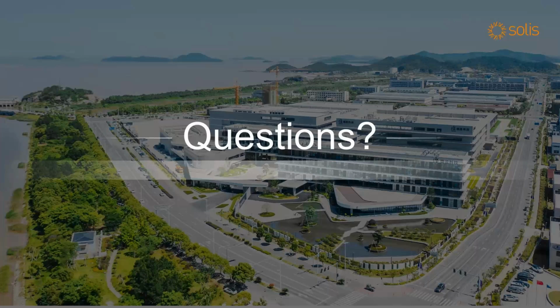And my final recommendation on that, Jason, is that if you look at our data sheets, you'll see that all of our inverters have a DC voltage rating. For example, on our hybrids it's around 330 volts. And then you'll see that it has a max input current. This is the max current that you can send to our MPPT without clipping. So for example, on the 14 amp 10K inverter, 330 times 14 amps is about 4,600 watts. That's what you can do to always determine the manufacturer's recommended power limit for any of our MPPTs. So take a look at our data sheets and you'll see, again, rated DC voltage and max input current for the MPPT.